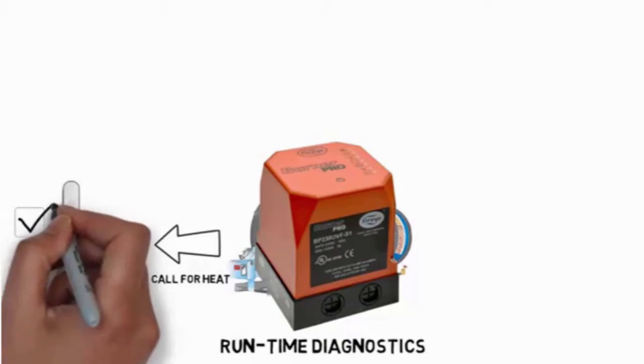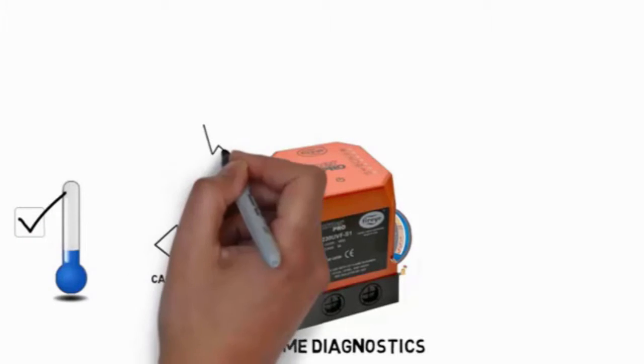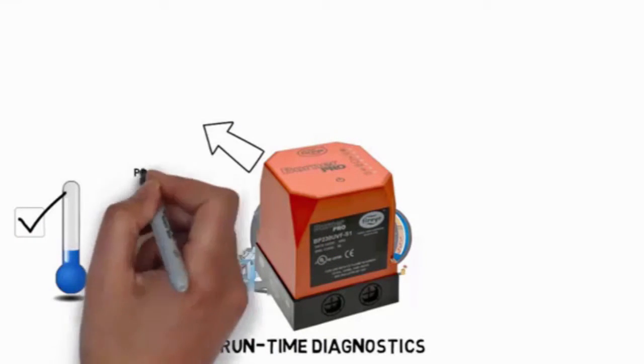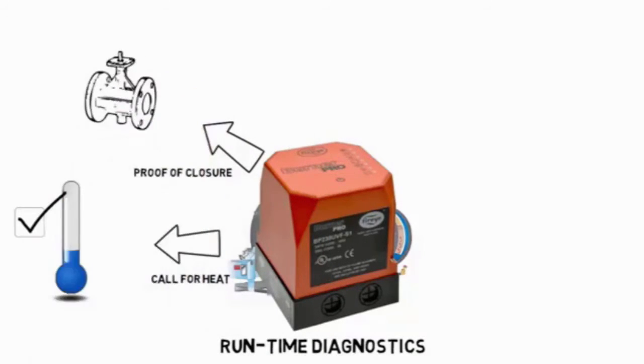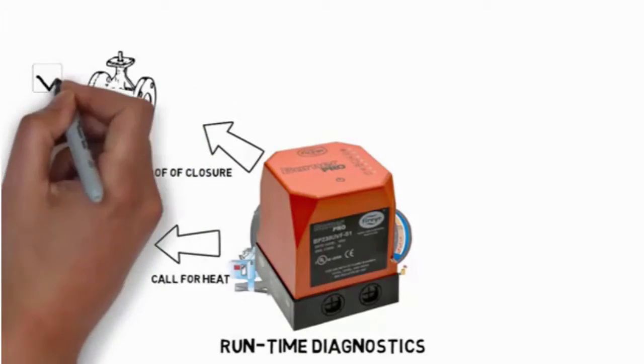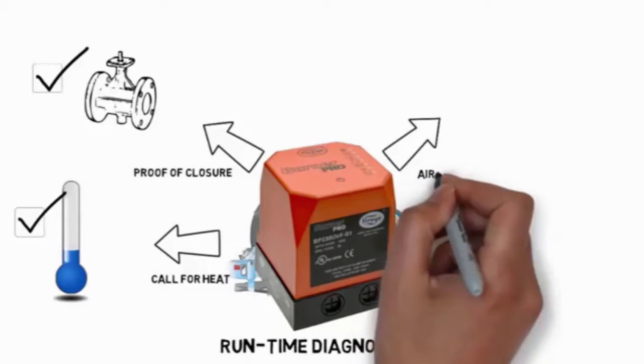the system turns on the combustion air blower and commands the actuator to move to the purge position. Proof of valve closure checks for wiring problems or faulty fuel valves. Air flow proving cycle ensures a proper combustion environment.